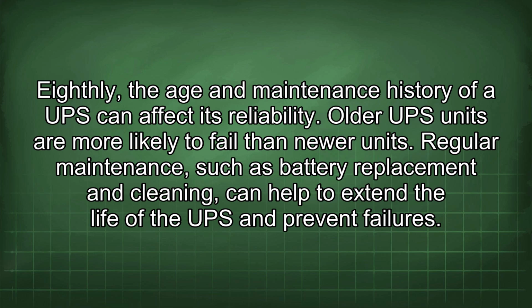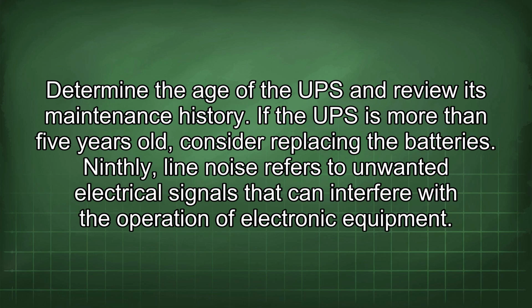Eighthly, the age and maintenance history of a UPS can affect its reliability. Older UPS units are more likely to fail than newer units. Regular maintenance, such as battery replacement and cleaning, can help to extend the life of the UPS and prevent failures. Determine the age of the UPS and review its maintenance history. If the UPS is more than 5 years old, consider replacing the batteries.